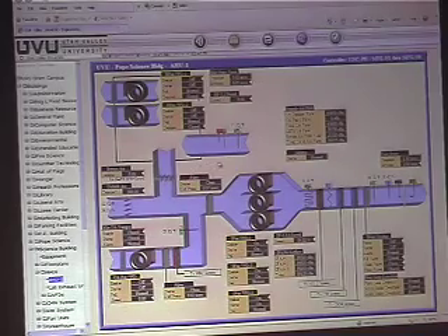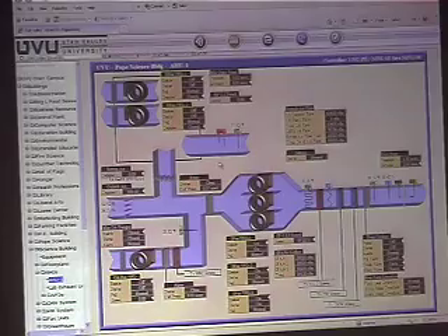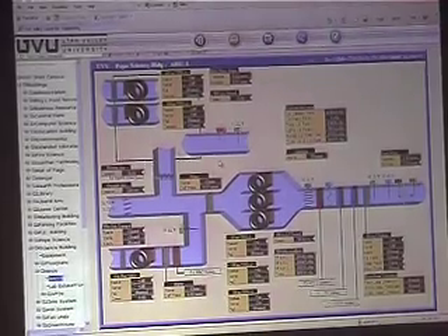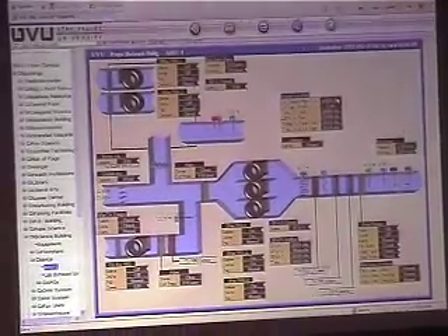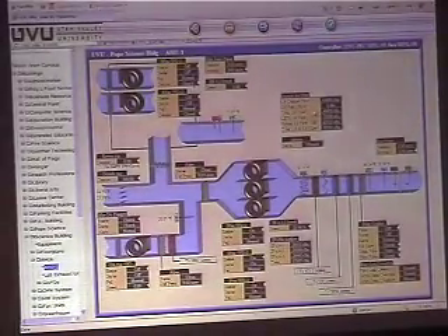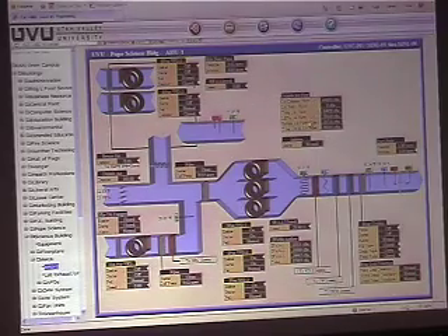So on the return air, what is it? Is it controlled based on mixed air temp or what's it? The economizer is a factor in it, in that if the dampers are allowed to cut back based on flow being satisfied, then the economizer, if it's calling for more, or less return and more outside air, then whichever the greater demand is what will control it. So you got your outside air damper flow here, your outside air fan flow listed, total outside air, and then lab exhaust, your return air calculated, and then total outside air and return air.